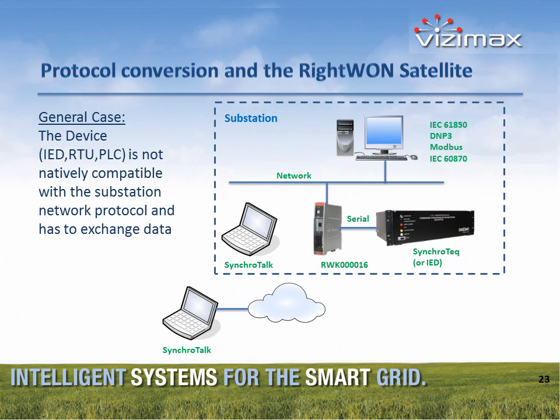As mentioned earlier, the RightWON can be used for protocol conversion. For example, the SynchroTeq control switching device uses a serial link with the SynchroTalk communication protocol, and the RightWON product converts that protocol to IEC 61850, DNP3, Modbus, and even IEC 60870 simultaneously, enabling a SCADA system to communicate with the SynchroTeq device directly.